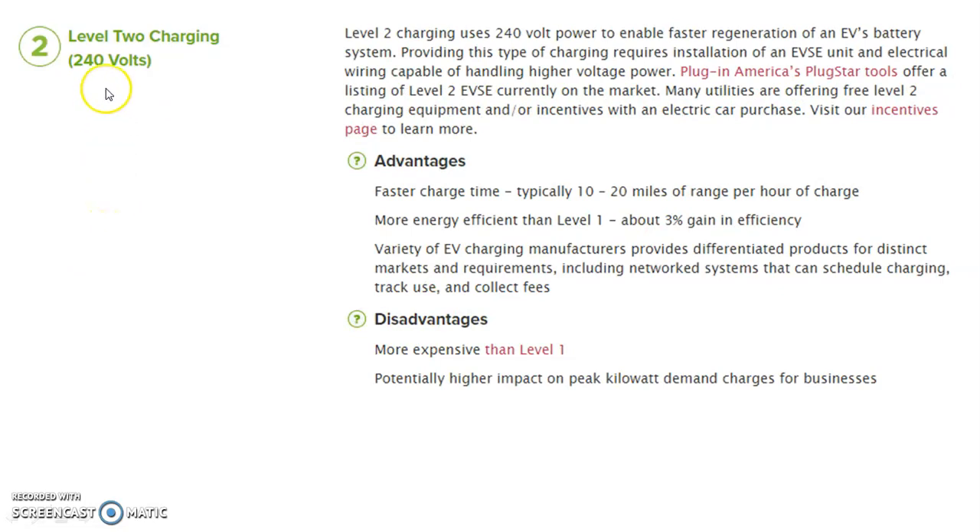Level two charging uses 240 volt power to enable faster regeneration of the electric vehicle battery system. Providing this type of charging requires installation of an EVSE unit and electrical wiring capable of handling higher voltage power. Advantages include faster charging time, typically 10 to 20 miles of range per hour of charge, and it is more energy efficient than level one — about 3% gain in efficiency. A variety of EV charging manufacturers provide differentiated products including networked systems that can schedule charging, track use, and collect fees. Disadvantages include higher cost than level one and potentially higher impact on peak kilowatt demand charges for businesses.